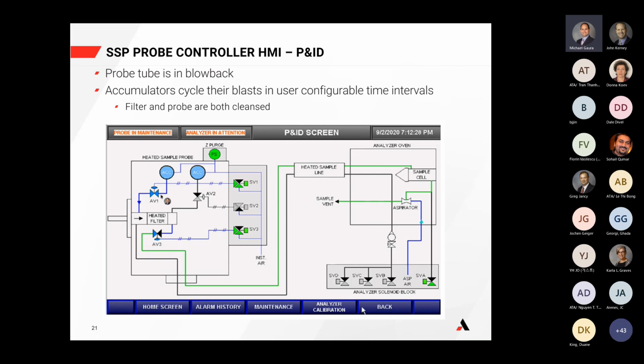The second accumulator is now active. So it's building off of that first blow from the heated filter accumulator. It's continuing to push particulates back into the process and getting them out of the probe assembly here. You'll note that this third solenoid and actuation valve here has changed status. We are no longer allowing the sample gas to run all the way down to the sample cell. We've closed this pathway off, and we're running a light instrument air purge through here to prevent any of these purged particulates that might work their way through here from eventually getting into the sample path. So we've got a little bit of air going through here, up here, and that's going out here. The ultimate goal here is to clean both the probe tube and the heated filter right here.